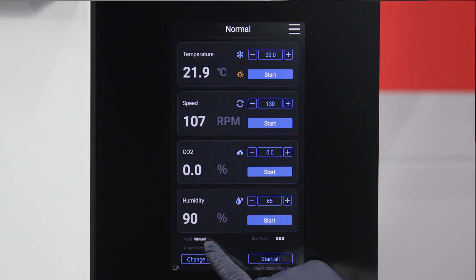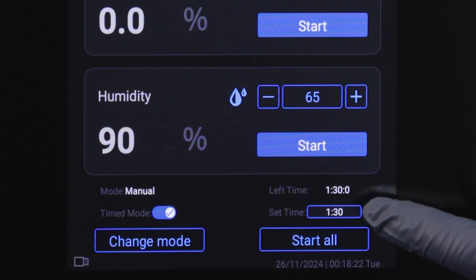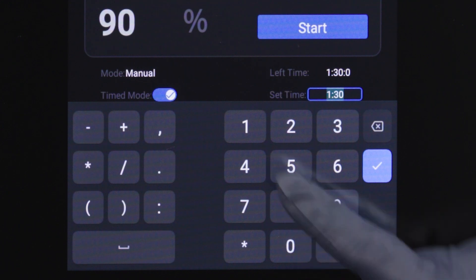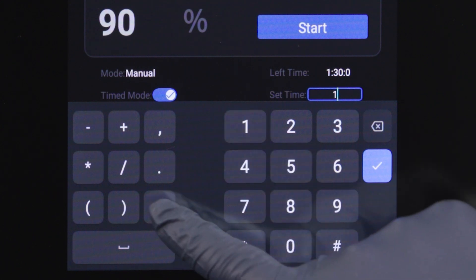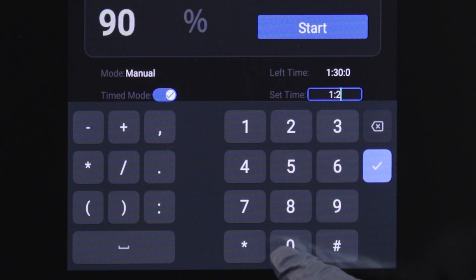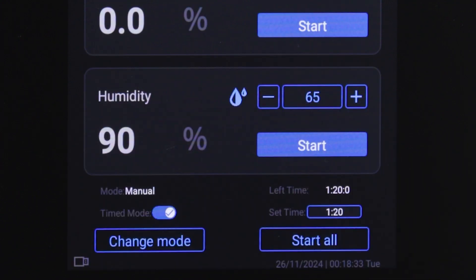If you turn timed mode on, the shaker will be in manual timed mode. In this mode, you'll need to set the desired runtime by entering values in the set time indicator. Tap the indicator and a numeric keypad will open where you can enter the number of hours, a colon, and the number of minutes. Tap the check icon after you've entered your desired settings.